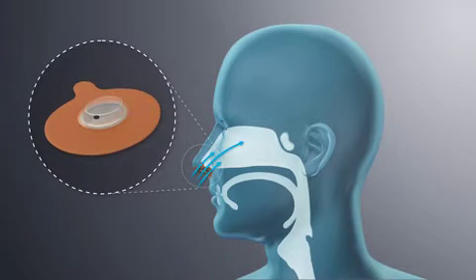During inspiration, the micro-valve opens, allowing for nearly unobstructed airflow. Then, during expiration, the micro-valve closes, partially restricting airflow to create EPAP and maintain pressure in the airway through the start of the next inspiration. This helps maintain airway patency during sleep.